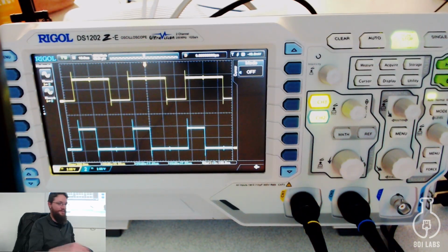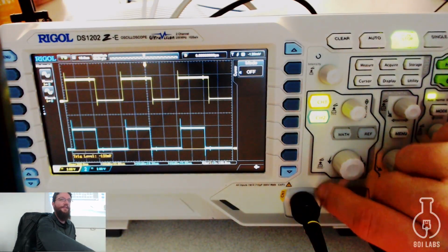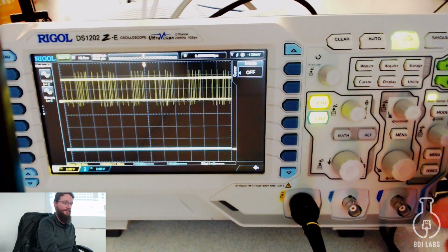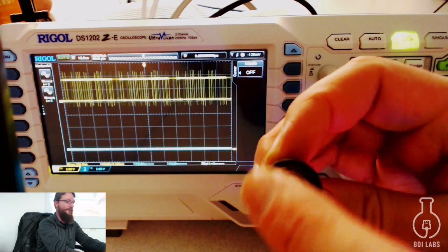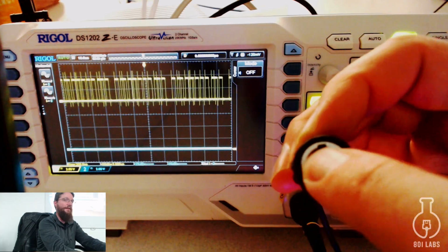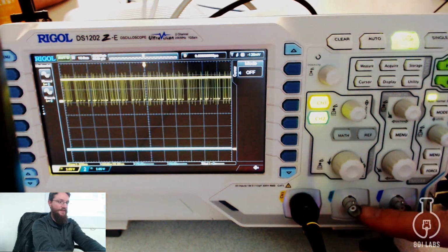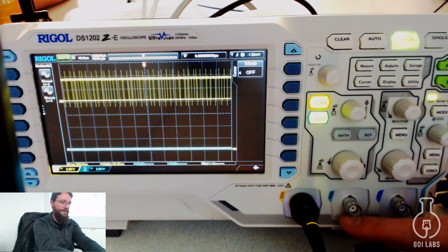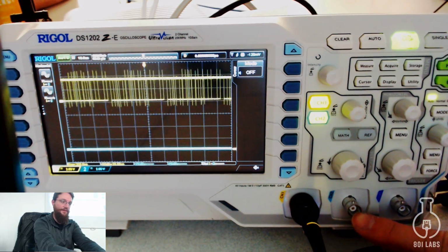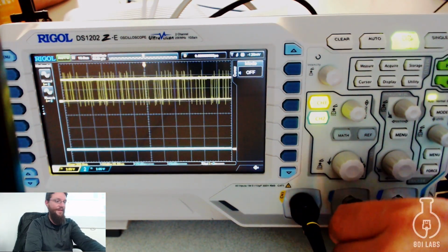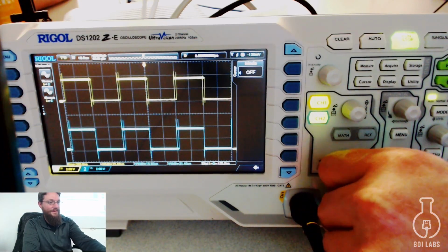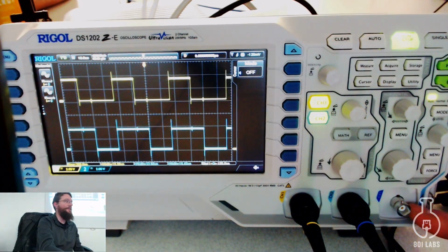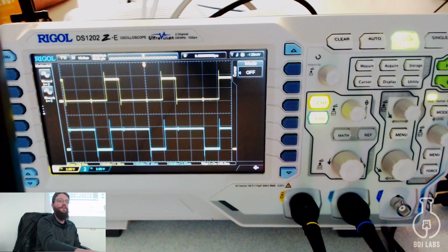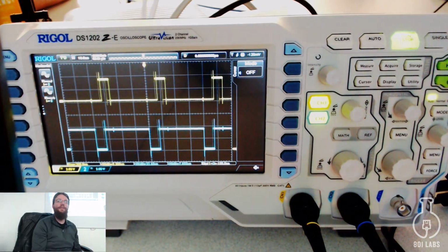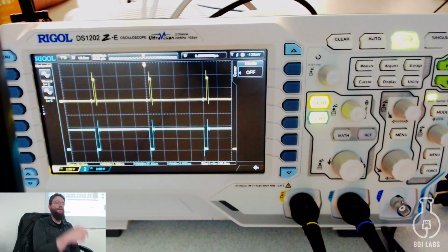So, one thing you should be aware of is the physical scope probes here that are connected via these BNC connectors. They have an outer shielding ring and the inner signal ring. That shielding is connected to the shielding on this connector, and you can see there's a little golden signal pin on the inside. The importantest thing to note is that these outer shielding rings are connected through the internal scopes directly to your earth mains ground. That's the third pin on your outlets.